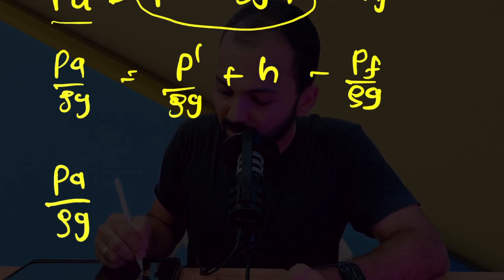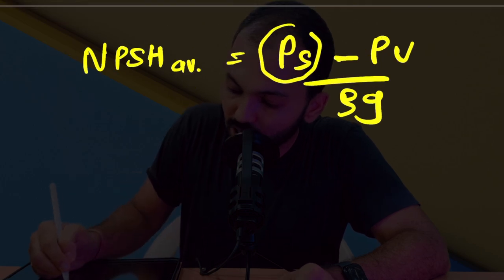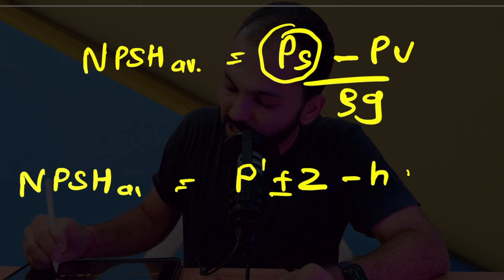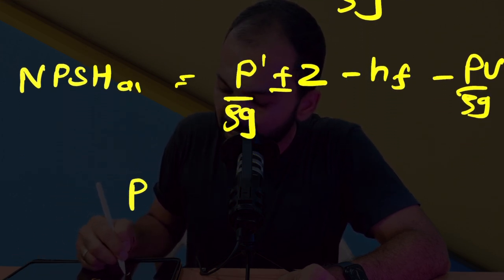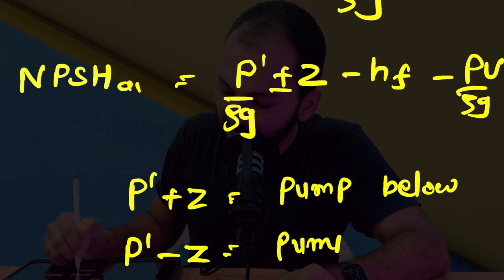Putting these values into the NPSH available equation: NPSH available = (p-dash ± z − hf − pv) / ρg. If we consider p-dash + z, that means the pump is below the liquid surface; if we consider p-dash − z, the pump is above the liquid level. This is how, by pressure balancing, we can calculate the pressure needed to find NPSH available, and confirm whether NPSH available is greater than NPSH required. In the next video, we will discuss all terms in the pump performance curve, characteristic curve, affinity law, and overall pump performance.